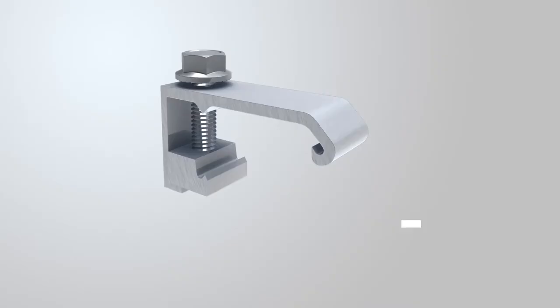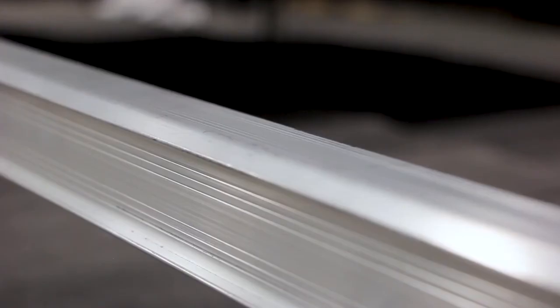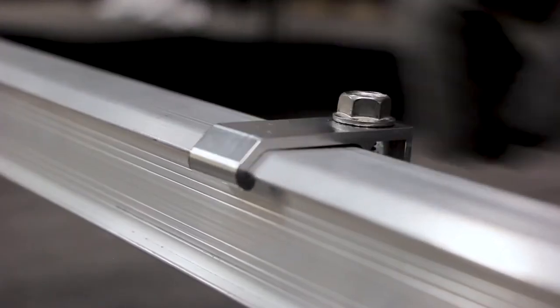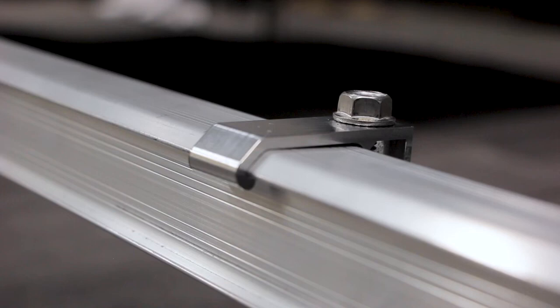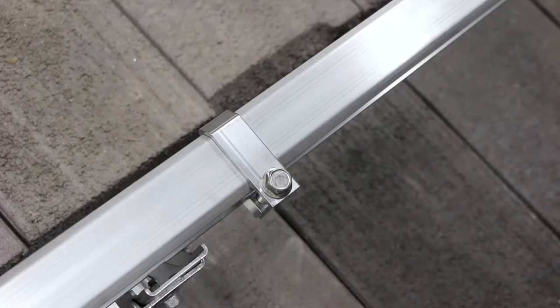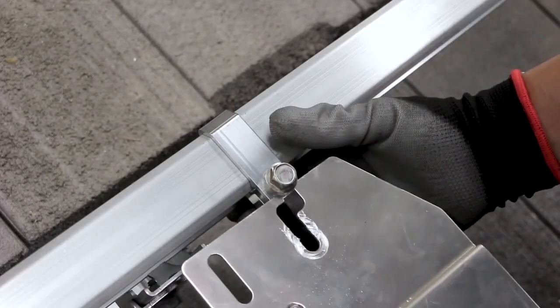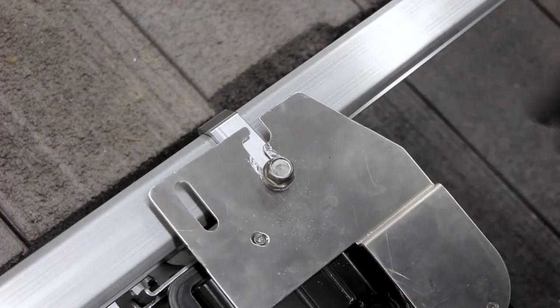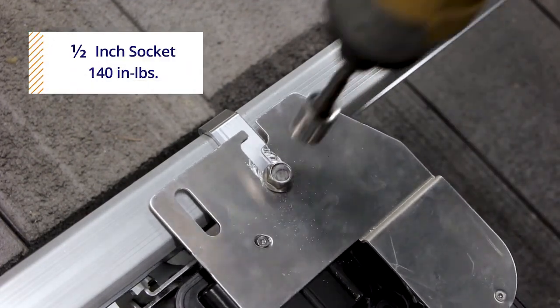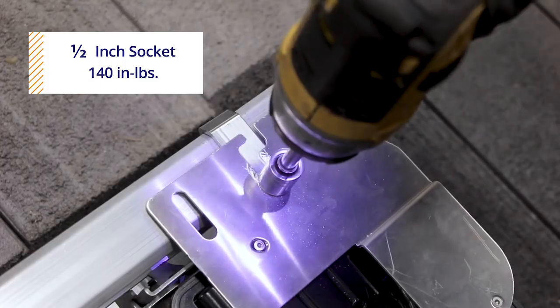rail. The MLPE bracket allows for microinverters and optimizers to be fastened directly to the ClickFit rail. To install, tilt and hook the bracket around the top flange of the rail and then set the bracket flush with the top of the rail. Slide the microinverter flange between the MLPE bracket and the serrated bolt flange. Tighten the bolt to 140 inch-pounds using a 1/2-inch socket.